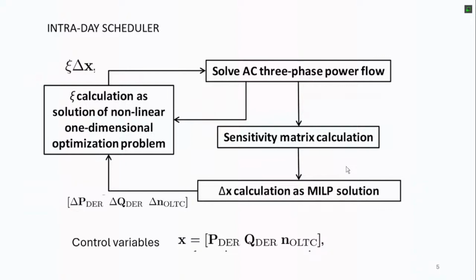Why three-phase? Because another difference of the distribution network with the transmission is that the imbalance and the not perfectly symmetrical configuration of the conductors are more significant than in the transmission network, which is in general more balanced and also symmetrical in operation. So we use this three-phase power flow, and from it we can also calculate the sensitivity matrix.